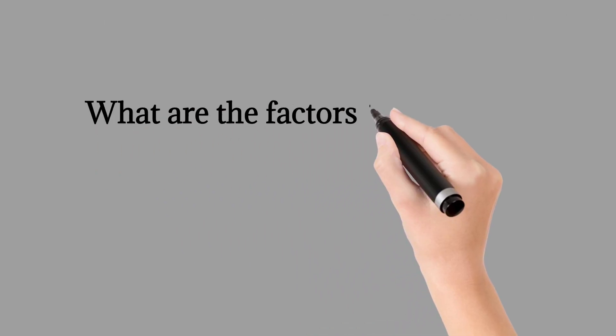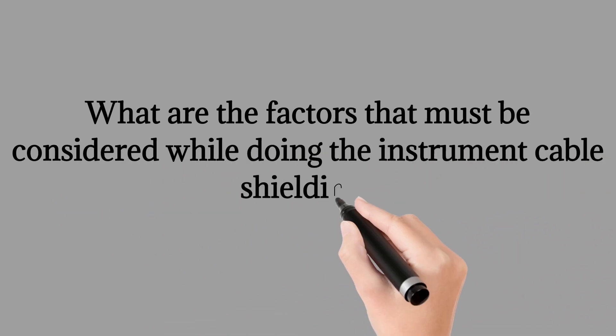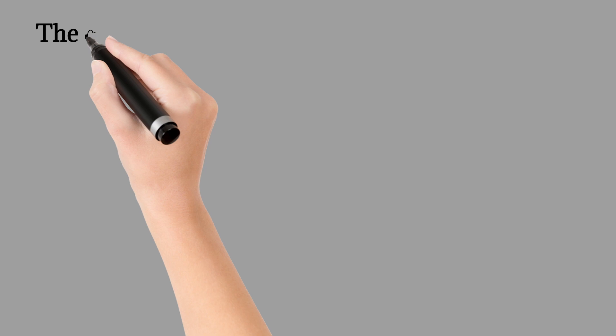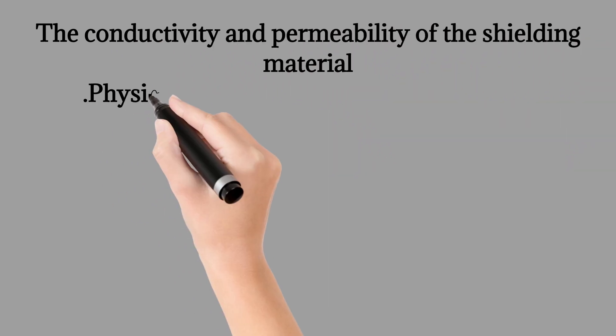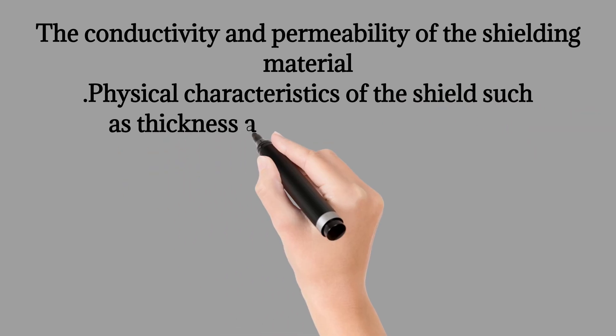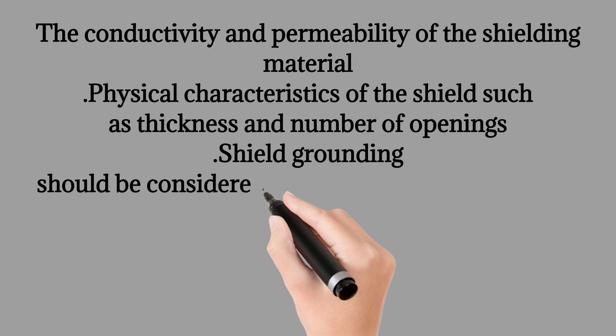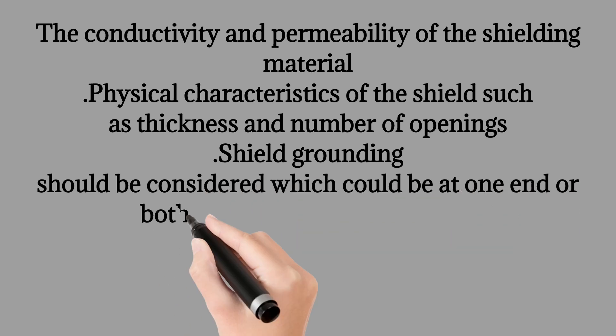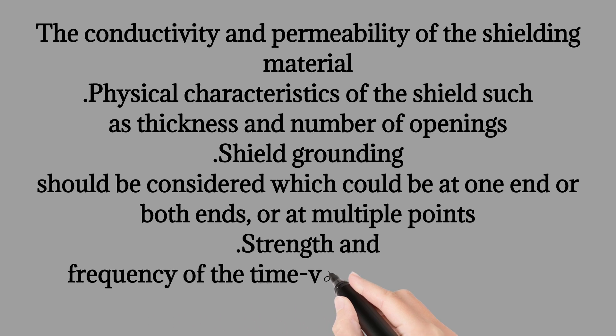What are the factors that must be considered while doing the instrument cable shielding? The conductivity and permeability of the shielding material, physical characteristics of the shield such as thickness and number of openings, shield grounding should be considered which could be at one end or both ends or at multiple points, strength and frequency of the time-varying magnetic field.